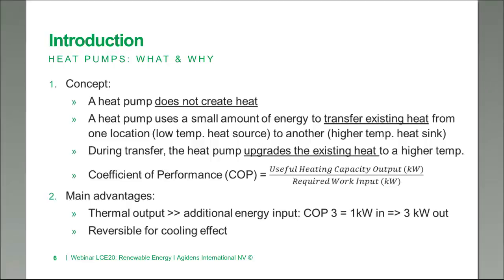It does so according to a certain coefficient of performance (COP). The higher the COP, the more useful heating capacity output you have gained compared to the required work input. The main advantage of the heat pump is that the thermal output is normally significantly larger than the additional energy input. If you have a COP of three, it means that you input one kilowatt of extra energy and you actually get three kilowatts out. An additional advantage is that in many cases the effect can also be reversed in order to cool certain processes.